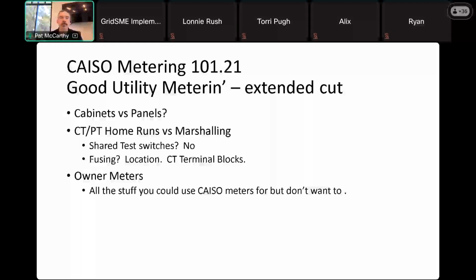So, design considerations. Some definite no-nos: shared test switches. We don't want someone to be able to shut off the utility metering because they need to access CAISO metering, and we don't want the CAISO inspector to interfere with utility metering. We don't share devices that interrupt circuits, except for those not meant to be normally used, like a terminal block. For all you green design engineers, there are terminal blocks that are for current transformers—they're shuntable. Don't use a non-shuntable terminal block, please.